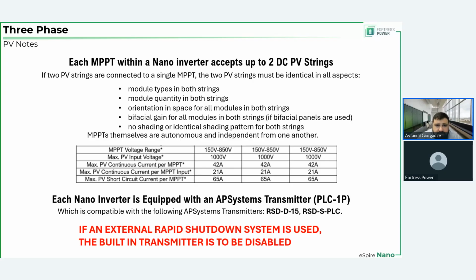If 2 PV strings are connected to a single MPPT, the 2 PV strings must be identical in all aspects. Those aspects are listed right here, and this is a rule. No shading. The module type per string must be the same. Module quantity per string must be the same. String orientation in space, or each module in each string, has to have the same orientation in space as all the other strings, right? Or all the other modules, sorry.